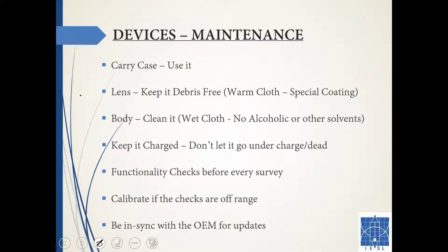You can use a local vendor for verification like ITI. I have seen some reports, but ITI cannot calibrate your imager. They cannot calibrate your imager. Calibration is a factory adjustment. If they find that the verification is off, they will calibrate it for you. You will have to send your camera back to the manufacturer or their designated laboratory for calibration checks.